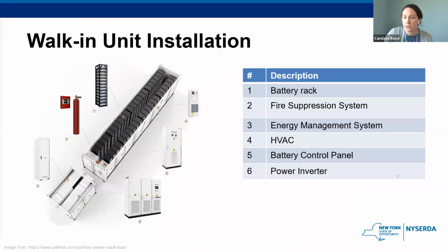So continuing, this is just another example of what a walk-in unit looks like. And like I said, this is likely what you'll be seeing the majority of when applicants come in with a 2 megawatt or 5 megawatt solar project. A lot of them are now looking to pair it with energy storage, and these are usually the system sizes they're looking to do as well. Once again, they have the fire suppression system, an energy management system, HVAC. You can see the battery rack, how it's situated. And definitely, you don't want to be in there if you don't have to be.